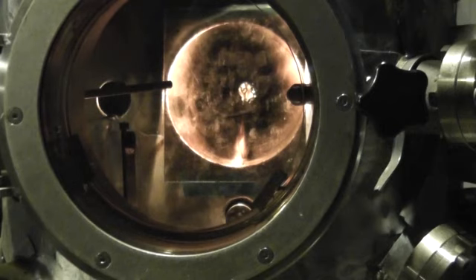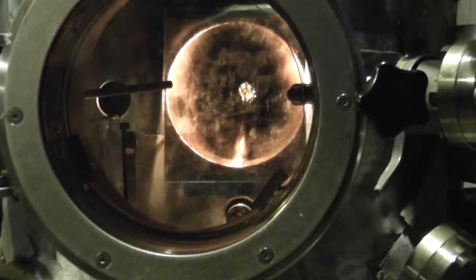And if nothing else, it's acting like a great getter. Now the pressure is dropping. It was about 5 and change times e to the minus 6 millibar, and it's now below 1.6 times e to the minus 6 millibar. So we're making a titanium sublimation getter pump here.